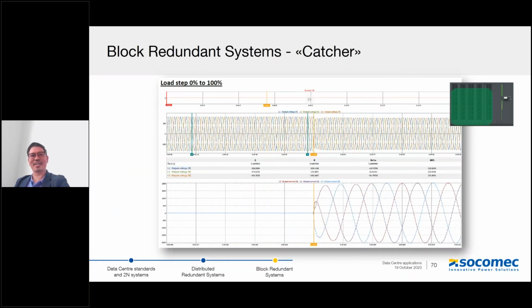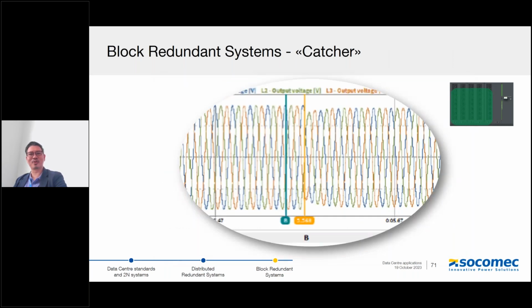We have done this testing on one of our major customers, and they are happy with the result. We have a catcher solution in the factory with an STS, and we captured it, we tested it, and if we zoom closely on how the system interacts, it's almost milliseconds. So the load will not be able to see any disturbance in the system.